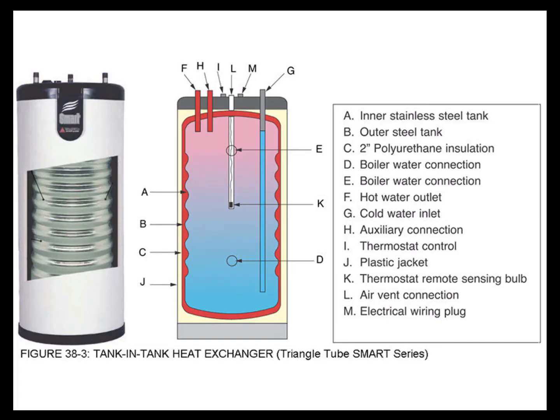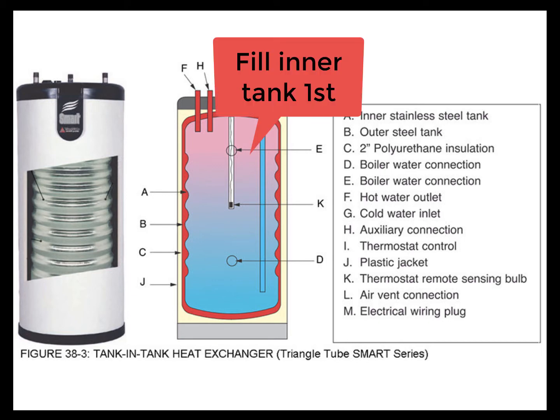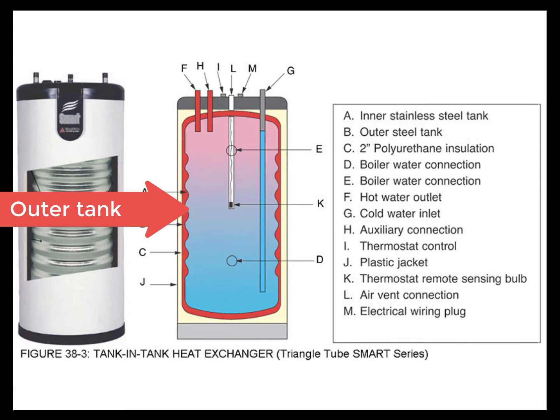Now depicted on the screen is a triangle tube smart tank. This is a tank within a tank design. It is important to follow the manufacturer's instructions as it pertains to filling. They require that the inner tank be filled first before you fill and pressurize the outer tank, which basically is the annulus between the internal stainless tank and the outer mild steel tank.